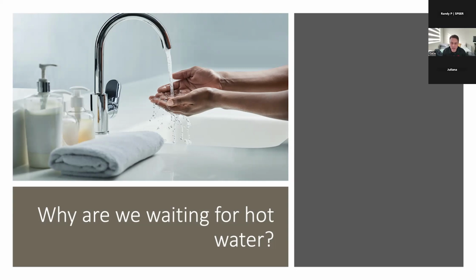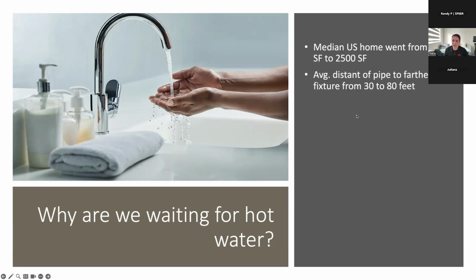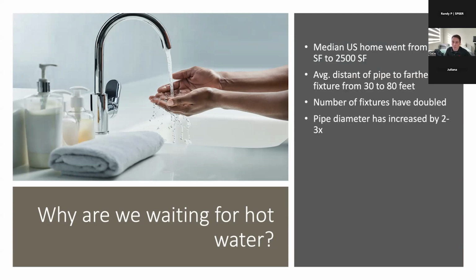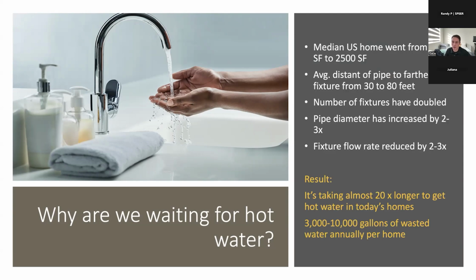And so here's the answer as to why we're waiting for hot water, particularly in new construction. Over the years, the median US home has gone from about 1,600 square feet on average to about 2,500 square feet. And so the average distance from the water heater to the farthest fixture has more than doubled. The number of fixtures has doubled. Pipe diameter has increased by a magnitude of 2 to 3 times. And fixture flow rate has been reduced by a magnitude of 2 to 3 times. So you take all of these things into consideration, right?